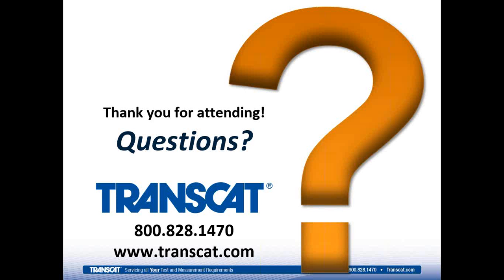Okay, great. And we had a question about RSS applications. I'm not sure if we got into that at all, or if that's something that you're familiar with. Yeah, RSS is the root sum square. It's a mathematical computation to pretty much average out the effects of different values. So if I was going to combine, let's say I'm taking a measurement that has a couple of instruments that are used in the measurement process to get the final measurement, I would have to somehow combine those 2 values to get the denominator tolerance for the PAR calculation. I would RSS those together, or do a root sum square of those values. I take each value of the tolerance that the manufacturer states for each of those instruments. I would square those values, I'd add them together, and then I'd take the square root of that. That would give me an RSS value for that denominator in the PAR calculation.